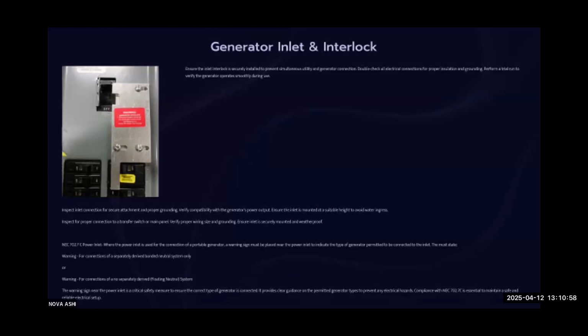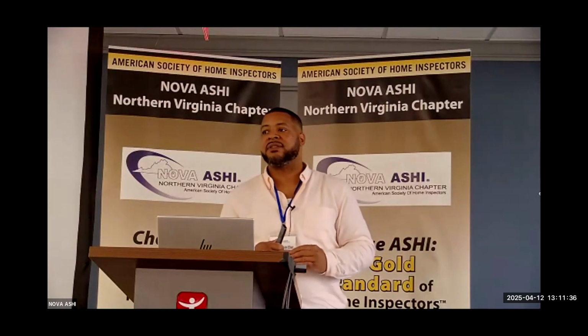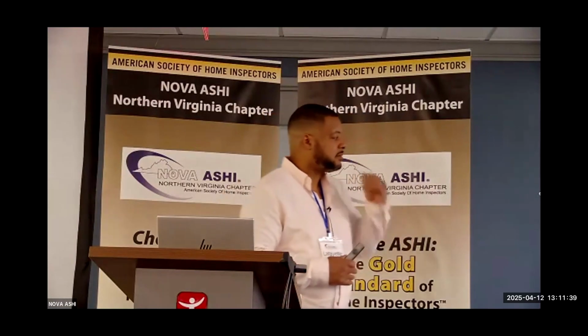One thing you learn reading up on this is it's a safety measure, not just to prevent something like a phase-to-phase fault between generator power and the electrical utility, but also because when the electrical is out, it's usually for a reason. If you feed power back through the metering system, somebody could be working on that line or transformer, and you could backfeed power to them and cause a shock or electrocution. So it protects not just you from a possible explosion at home, but also the electrical servicemen on the other end.